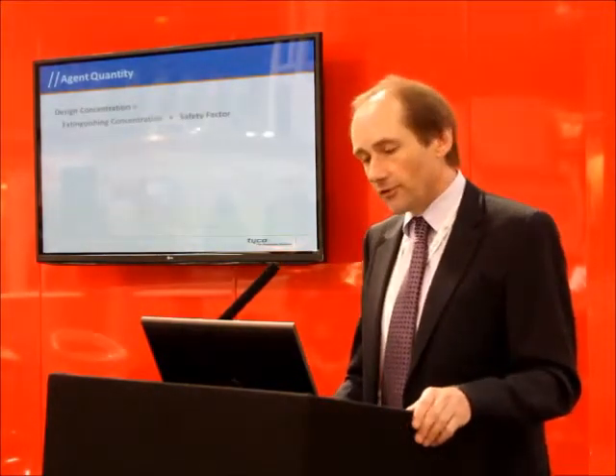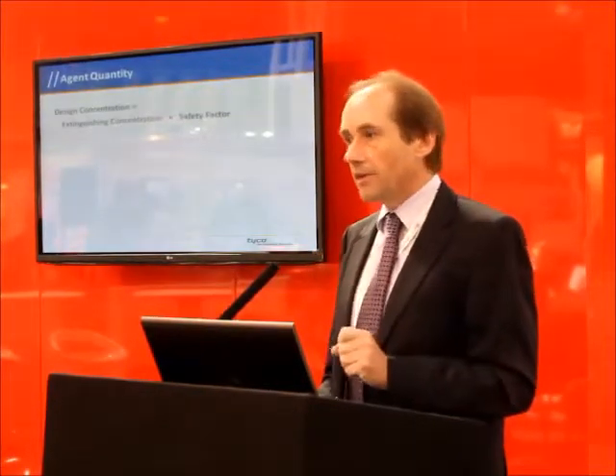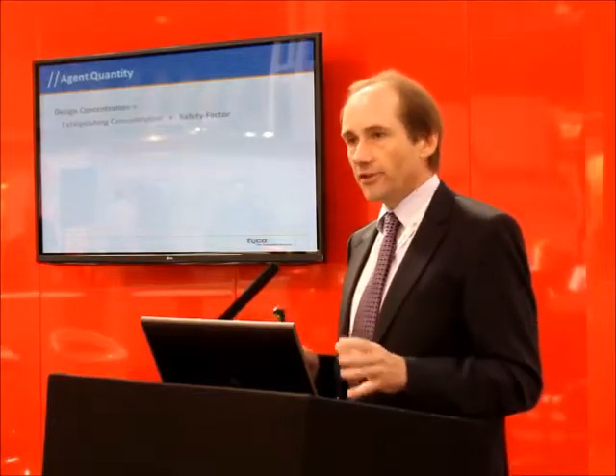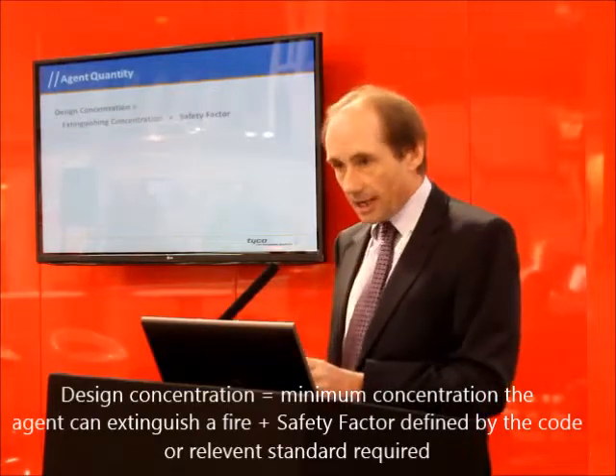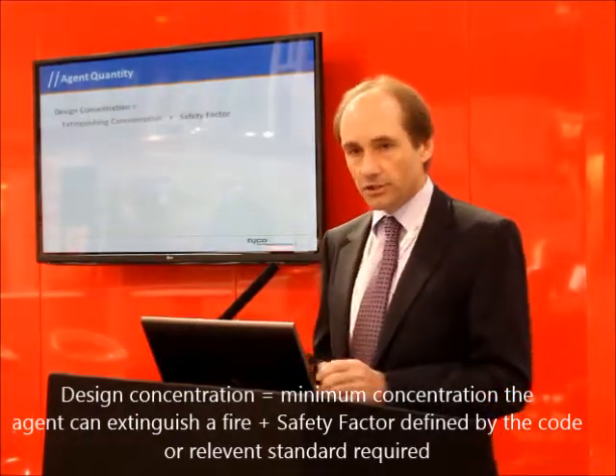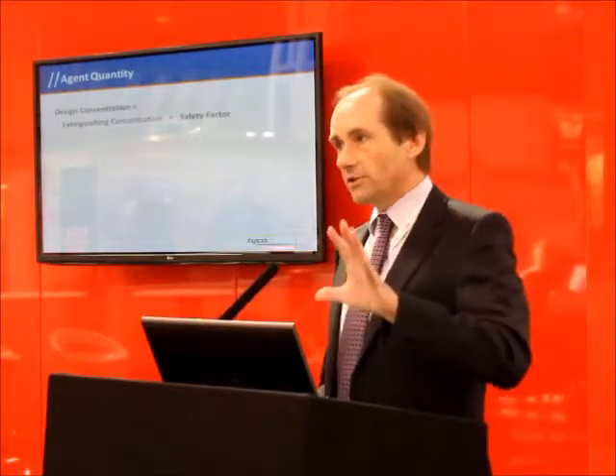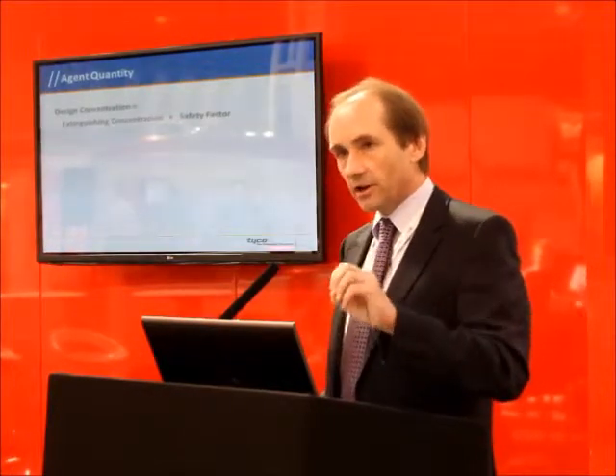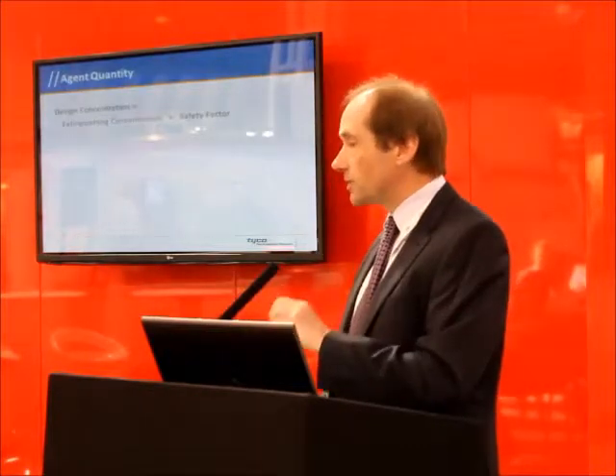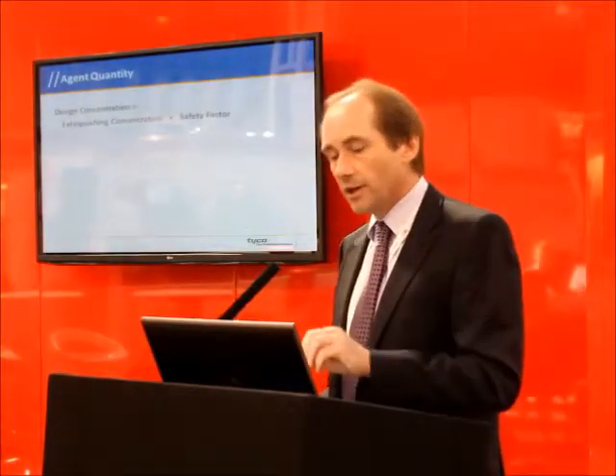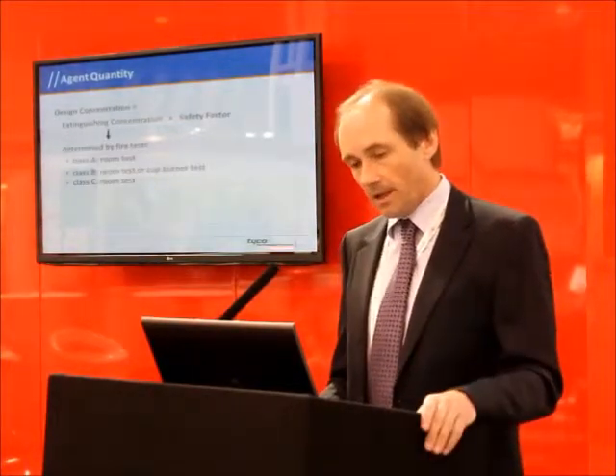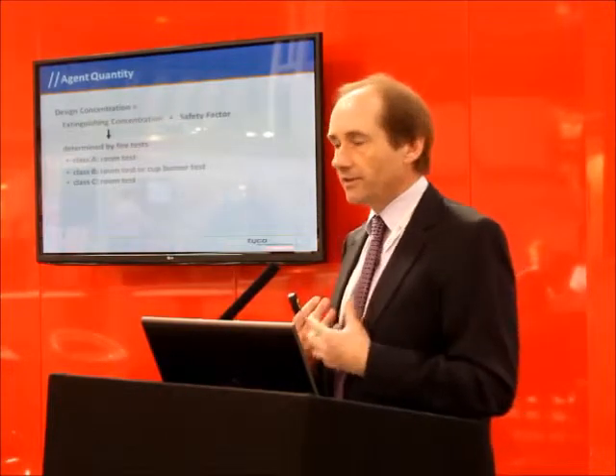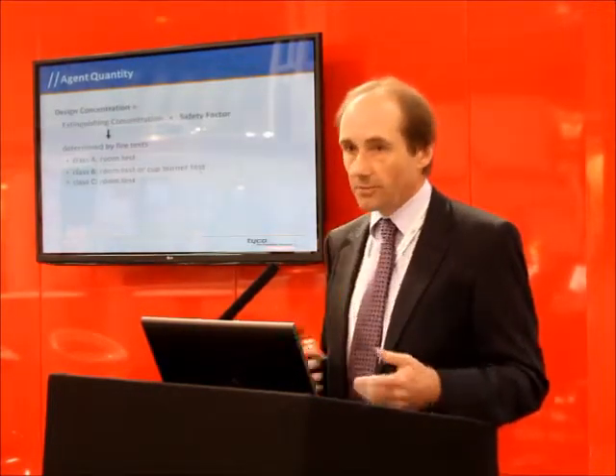So when we talk about design concentration, we're talking about two fundamental elements. The first one is the concentration at which that agent will extinguish a fire. And the second one is a safety factor that is applied. That safety factor varies according to some of the design standards. So when we talk about design concentration, we are typically talking about a concentration that includes the minimum extinguishing concentration plus the safety factor defined by the code or standard that you're working with. That extinguishing concentration is what we as manufacturers set out to determine when we introduce and develop a new system.